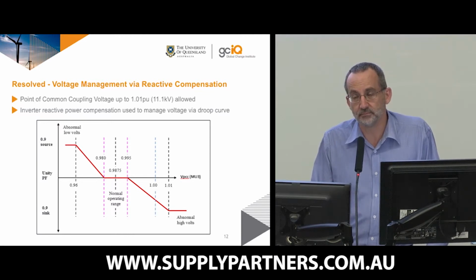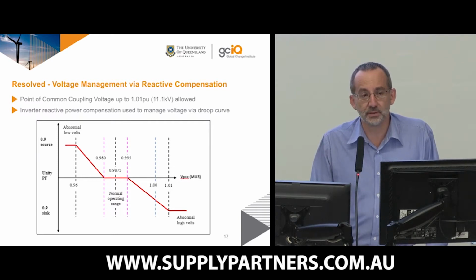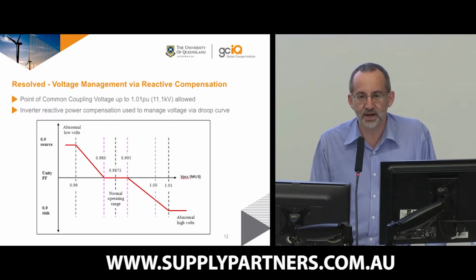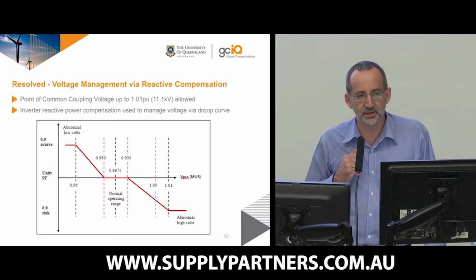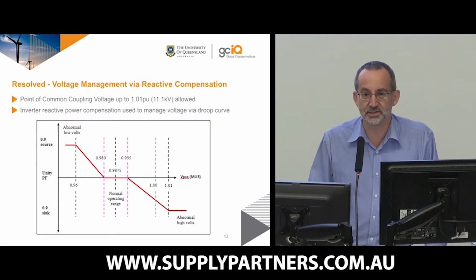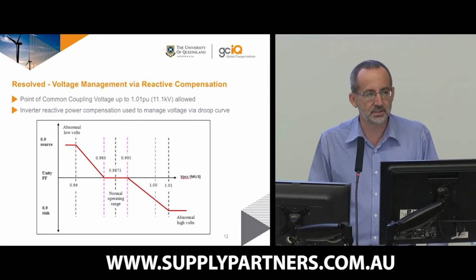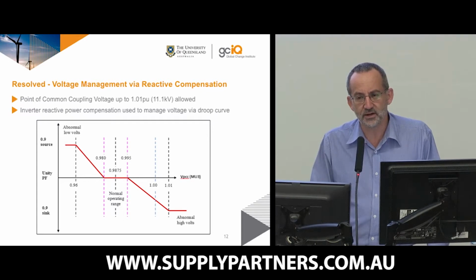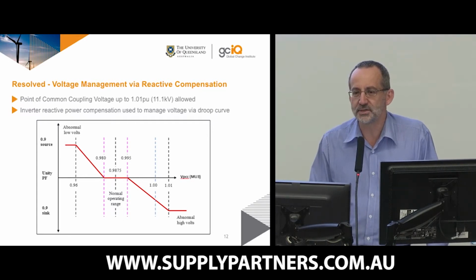Since earlier this year, the new connection standard in Queensland is trying to drive people toward configuring the inverters to 0.9, and I'm sure that a lot of inverter manufacturers will do that by default. I don't believe that's a good thing, because at the same time they've introduced a tariff to charge commercial customers for consuming reactive power. On one hand, they're saying it's bad, we're going to charge you for doing it. On the other hand, they're telling the PV installation industry, it's good, you better do it. You can't have both policies side by side. One of the consequences of consuming reactive power in the inverters is that someone will have to supply it. Someone will have to install capacitors on the substations, or generators will have to run in a fashion that can supply it. That will cost money, and guess who will end up paying for that?